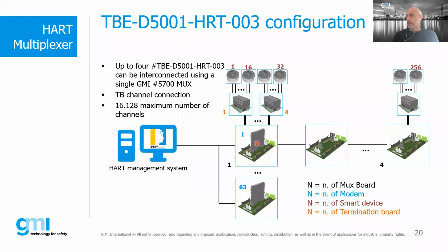In this case, it can be extended up to 4, which is what is needed for 256 channels. But as the interface is RS-485 Modbus, you can also multiply the number of multiplexer nodes, having up to 63 nodes, that is 63 multiplexers connected to just one HART management software.